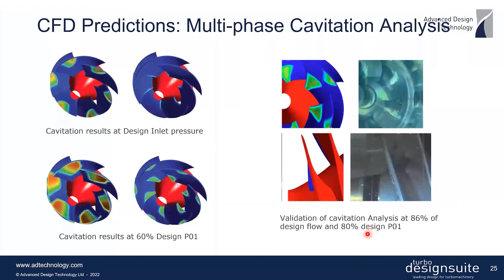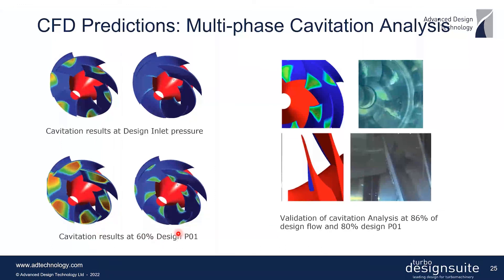They verified this using a multi-phase cavitation analysis. The contours show mass fraction of the vapor phase: blue means all liquid, while green or red indicates cavitation. The baseline impeller was cavitating at the inlet design pressure in several regions, but the new design was not cavitating at all at the inlet design pressure. At 60% of the inlet design pressure, cavitation expanded significantly in the baseline design, while the final design showed much improvement in the cavitating region. They also had access to a cavitation tunnel to verify their analysis.